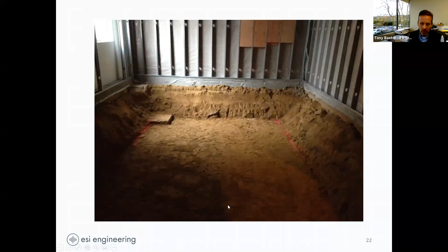We came back and made more vibration measurements. This might not be the best data, but I think it demonstrates the point. We measured on the little 3 foot by 3 foot slab they put back in the middle, on the column footing I showed you, and on the sidewalk outside the building. If you look at the peak vibration level here, it's about 175 micro Gs.